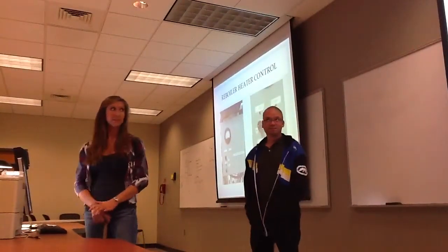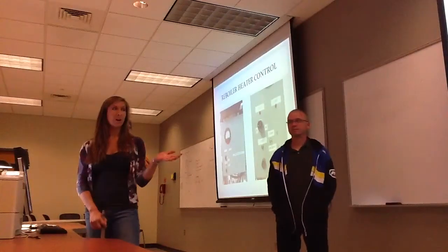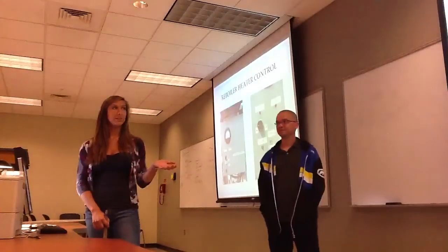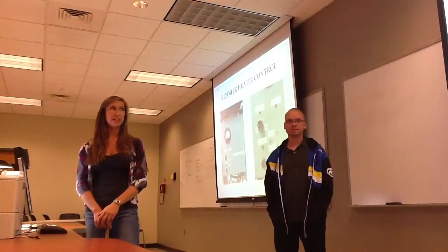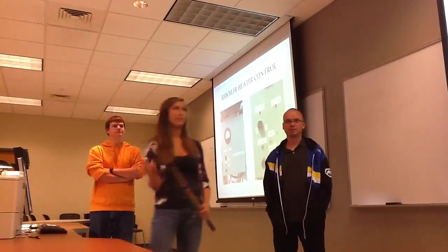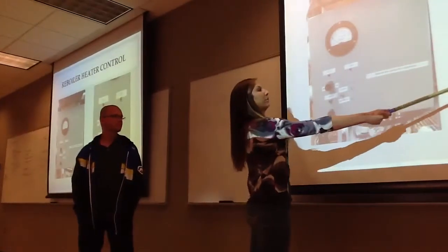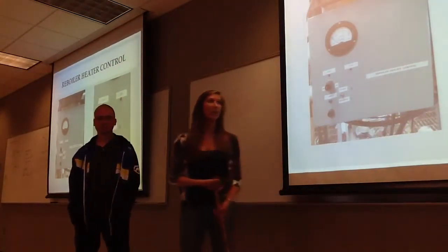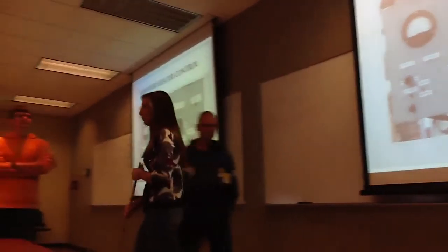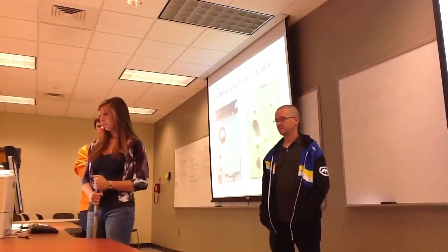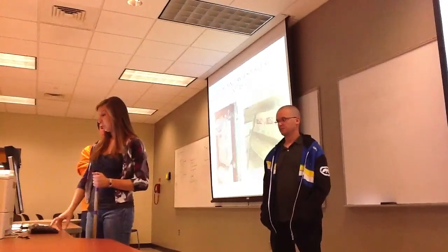This is the reboiler heater control. We've been having some difficulty with this as well. Sometimes it operates pretty well from the computer, and then sometimes it randomly has to be operated manually. And by flipping this knob right here, it goes from manual to computer. Last week it was working through the computer, and then it randomly decided to be run manually, and so that has also been an issue for us.